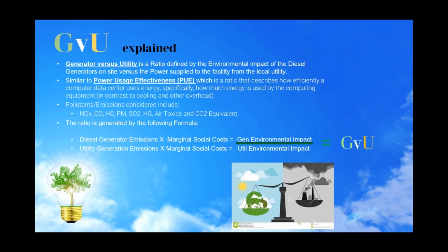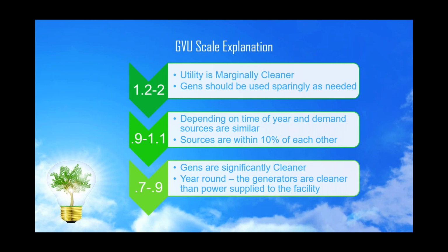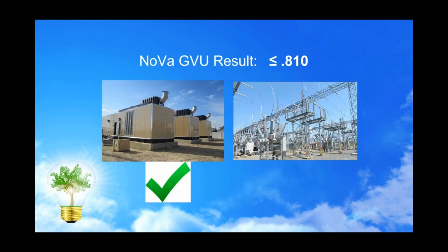When you run the calculation, if your ratio is 1.2 to 2, that means the utility is cleaner and you should use the diesel engine sparingly. If they're about 1 — 0.9 to 1.1 — they're within 10% of each other. So in the summertime, when the utility is using peakers, you know your diesel's cleaner; in the winter it might be the reverse. But if you're below 0.9 on this GVU parameter, you know the diesels are always going to be cleaner than the grid.